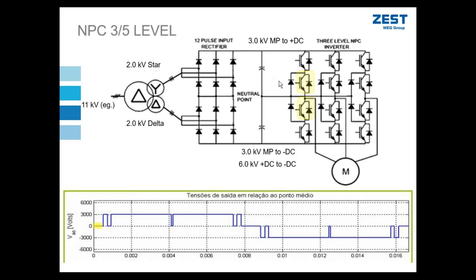So let me demonstrate that. If I fire the two inside IGBTs, this waveform that we're showing here is measuring from one phase to the motor and neutral point. So we're literally measuring the phase voltage in one phase. If I switch my two inside IGBTs, I have 0 volts going to my motor. So that is my 0 volt step.